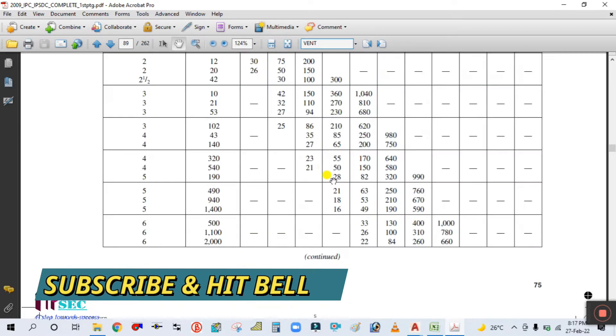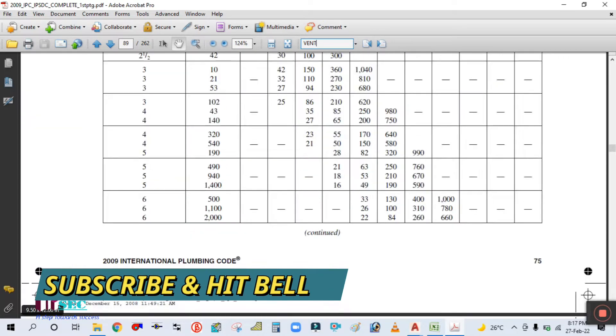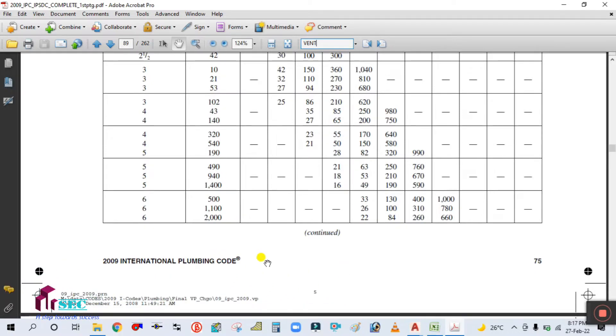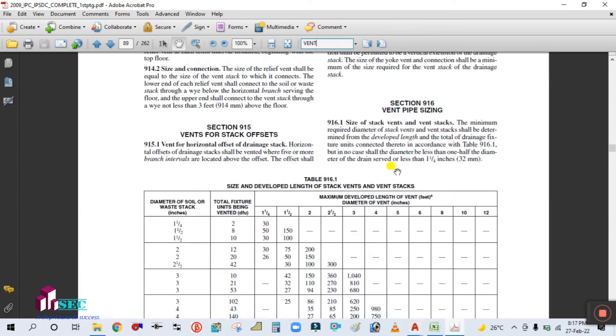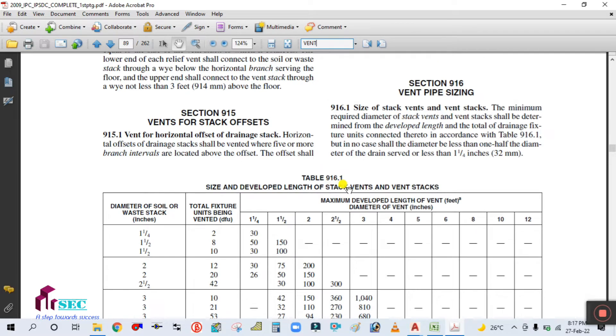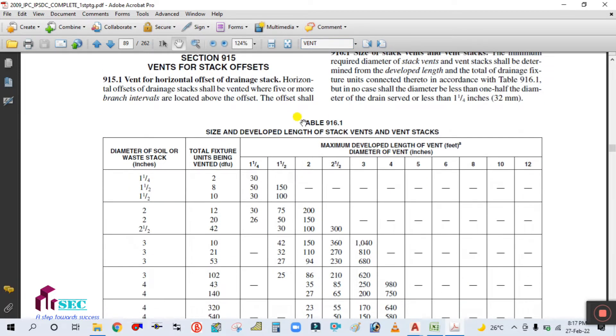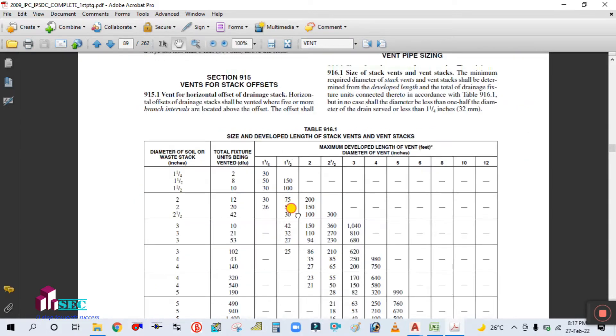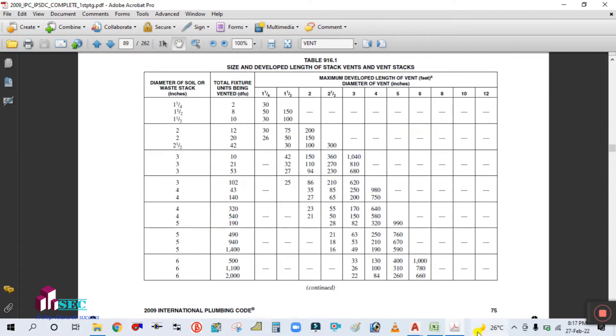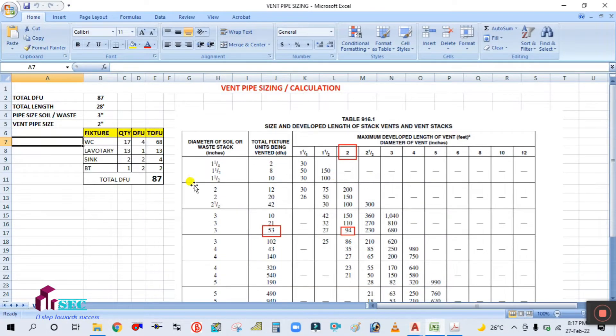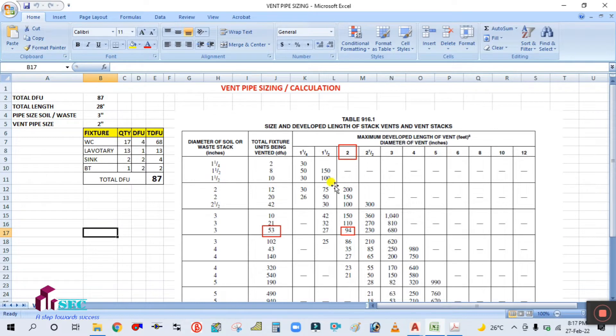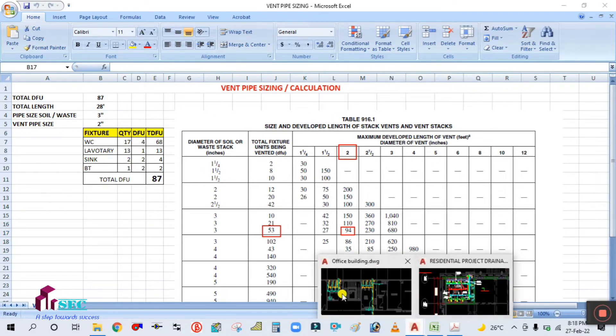Here, you can see this is from the 2009 International Plumbing Code, and this is Table 916.1 — Size and Developed Length of Stack Vent and Vent Stack. From here I have taken this table. So how to find the pipe size and the vent developed length? You can see in our project here.